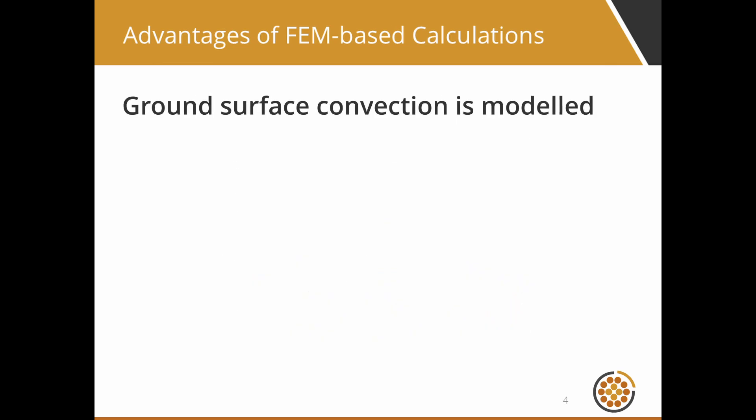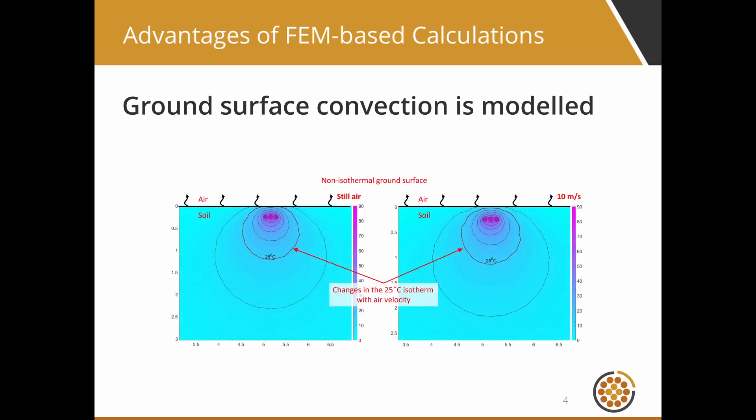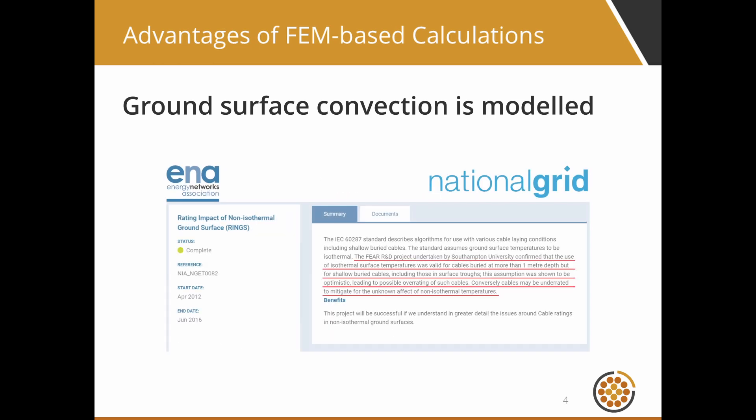Secondly, the heat transfer between the ground and air is modelled. The IEC standard assumes that no heat is transferred between the ground surface and the air above, known as the isothermal assumption. FEM, on the other hand, allows the convection of heat generated by buried cables — which flows into the ambient air — to be considered. For shallow buried cables, the difference in current ratings between the IEC standard and FEM is often significant.